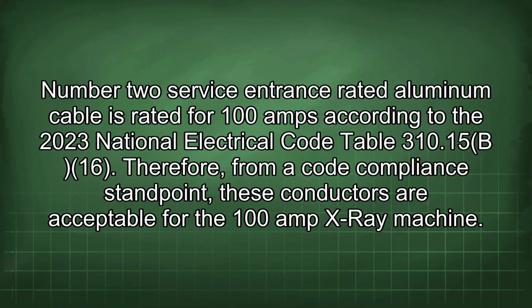Number 2 service entrance rated aluminum cable is rated for 100 amps according to the 2023 National Electrical Code Table 310.15(B)(16). Therefore, from a code compliance standpoint, these conductors are acceptable for the 100 amp X-ray machine.